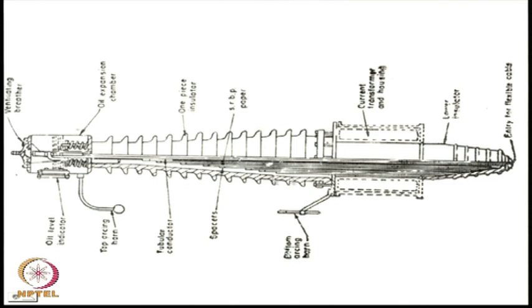This figure shows the construction of one type of bushing called the oil filled bushing. There are two types, the oil filled type or the capacitor type. This is for an outdoor transformer. The bushing in its simplest form is a housing, an insulated housing, mostly of porcelain, with a hollow space in between through which the connecting wire or the rod can be placed. So, this is the bushing. These are the porcelain discs which provide the insulation. So, from the top to the bottom, here is the entry of the cable and this is the conductor.